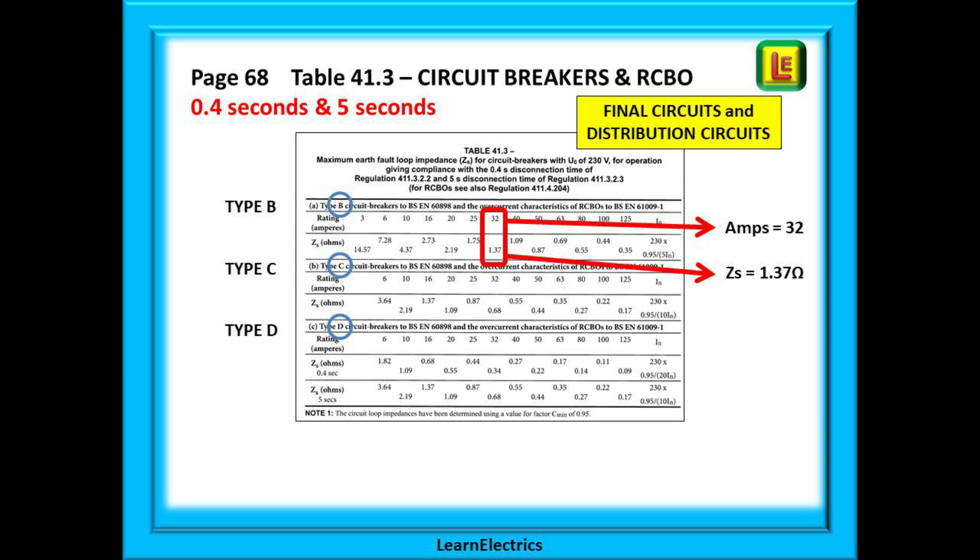Read the question. It will tell you the type. They all have different ZS values. We've highlighted in red a type B breaker of 32 amps rating. And vertically below 32 is the ZS value 1.37 ohms.